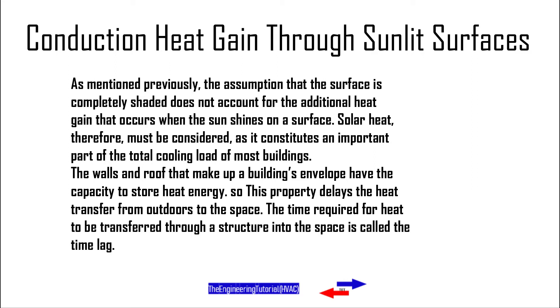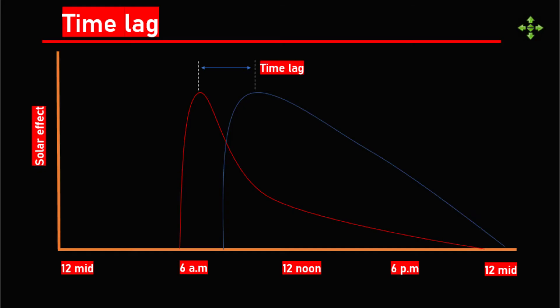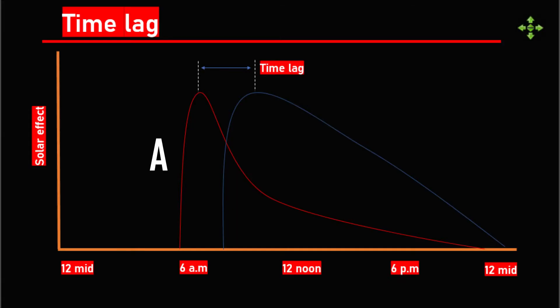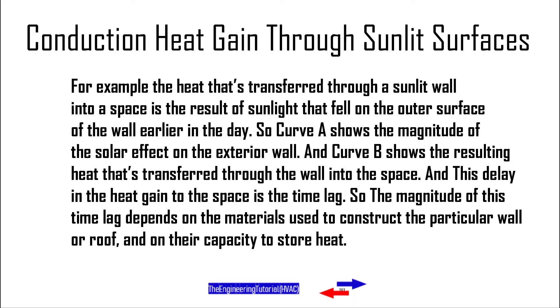The time required for heat to be transferred through a structure into the space is called the time lag. For example, the heat transferred through a sunlit wall enters a space as the result of sunlight that fell on the outer surface of the wall earlier in the day. Curve A shows the magnitude of the solar effect on the exterior wall, and curve B shows the resulting heat transferred through the wall into the space. This delay in heat gain to the space is the time lag, and its magnitude depends on the materials used to construct the wall or roof and their capacity to store heat.